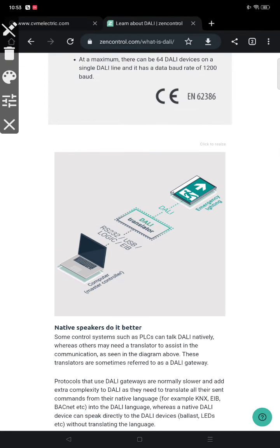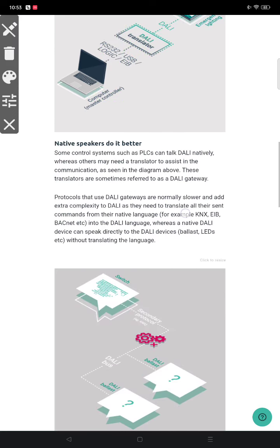So the DALI translator. This is the emergency lighting. This is the DALI cable. This is our emergency light. The DALI cable. The translator converts it into signals and logic, and then this is the computer which is controlling it. Native speakers do it better. Some control systems such as PLC can talk DALI natively. PLC is programmable logic controller, whereas others may need a translator to assist in the communication, as seen in the diagram above.